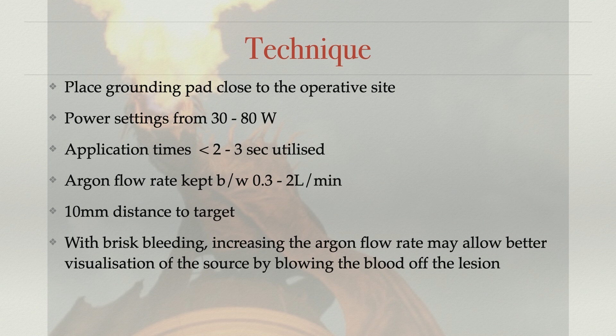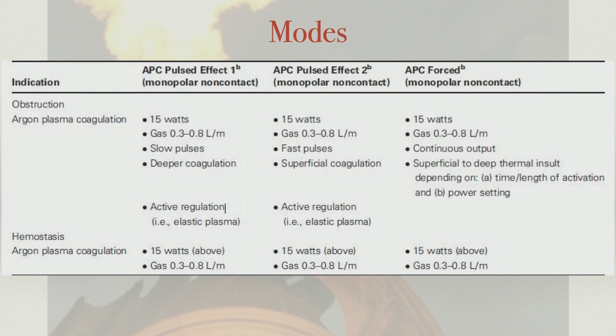Okay? Of course, there are 3 different modes. You have a pulsed effect mode 1, APC pulsed effect 2, and APC forced mode. So these are the 3 modes. If you look at the entire table, you will see that almost everything is the same except these aspects, where the effects will cause either a deeper coagulation, a superficial coagulation, or a superficial to deep thermal insult. So what these modes differ in is only the kind of after effect that will show up after doing the procedure. Otherwise, the argon plasma, the wattage, the hemostasis, everything is almost the same.